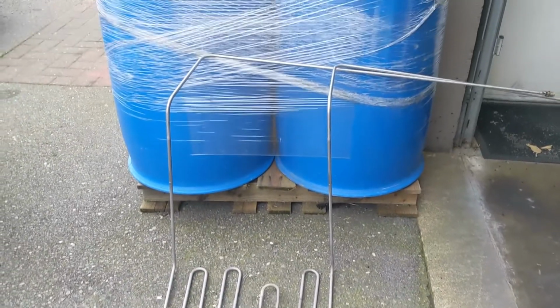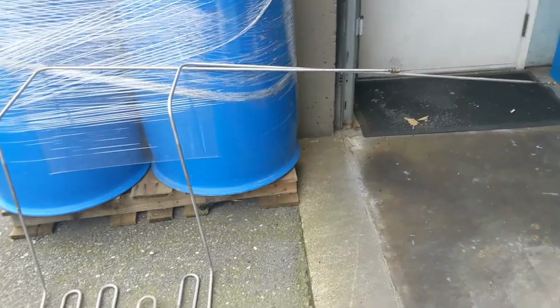The coil seems to be leaking. Maybe whatever's in that bath has been eating the stainless steel. We're not quite sure. So we had to remove the coil for them to repair it. And basically all that meant was to pump the system down and to undo the flare connections, let them do their welding thing. Then my dad went back the next day and reinstalled the coil for them.